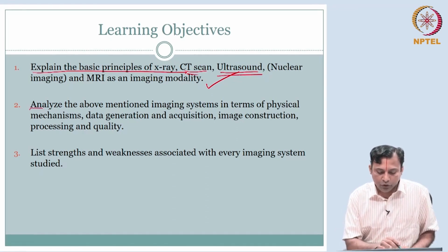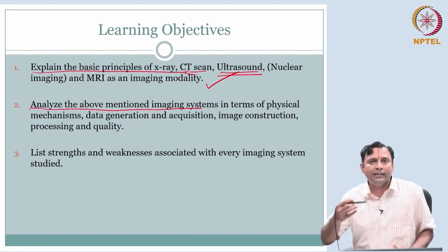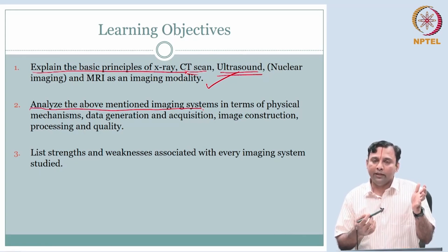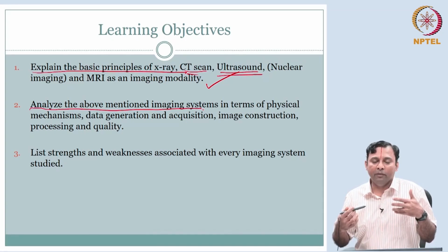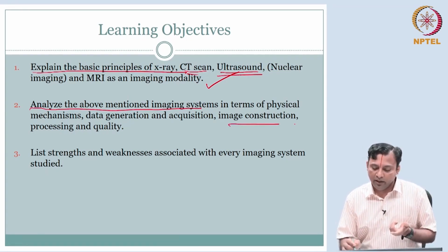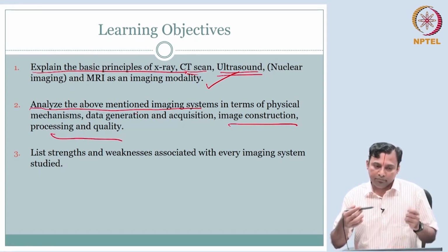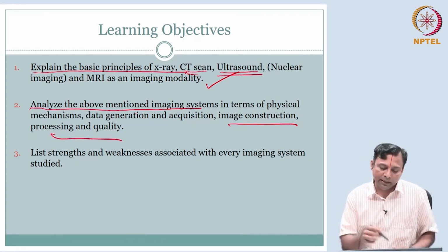To some extent, we should be able to analyze the system. When I say analyze, it is not analyzing the image, it is analyzing the system. What do we mean by analyzing the system? Is the image showing poor quality? Is there a dropout? Is it because the patient himself biologically does not have the signal there, or because the instrument probe is gone, or because of software? Any of that. So you should be able to analyze the output and understand the system and system settings that give rise to the image.